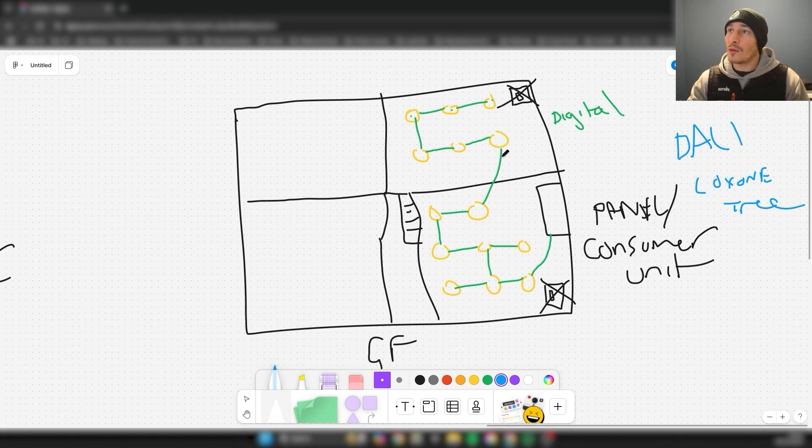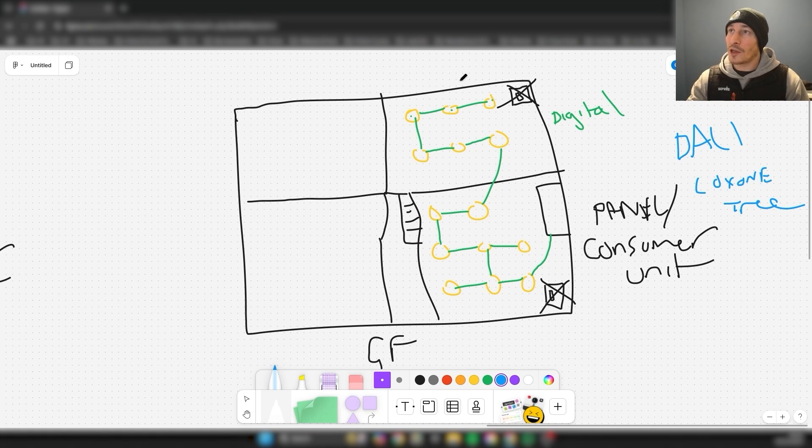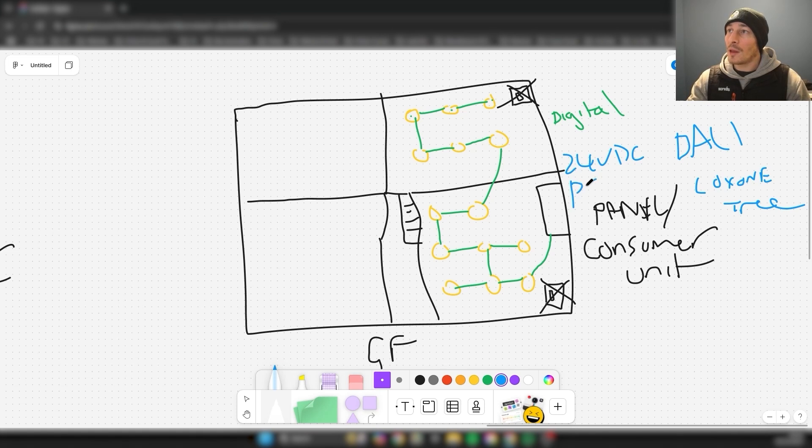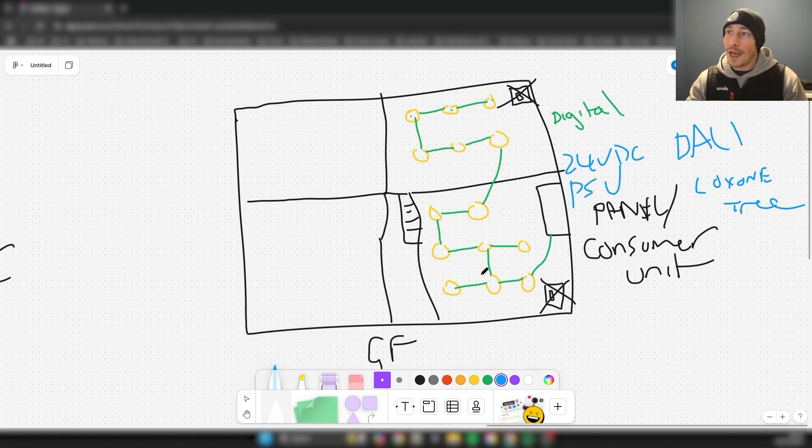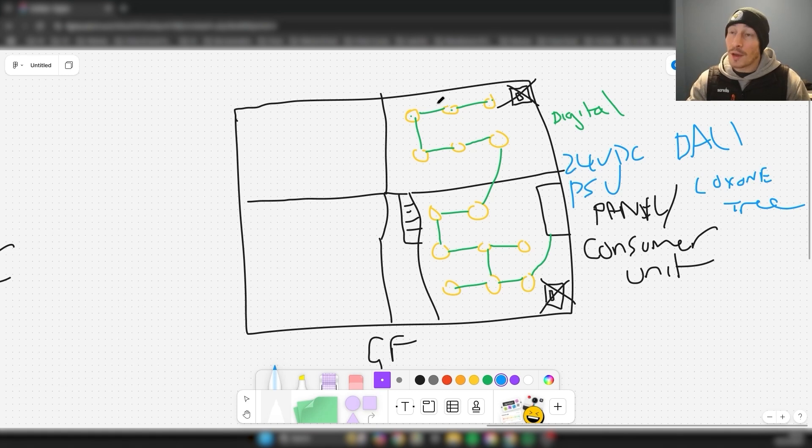You also need to be careful when you're doing it like this not to have too much power consumption. You need to think about, for example, if these are 24 volts DC, you need to make sure that the PSUs are spec'd correctly and can handle all of these lights if they all switch on.